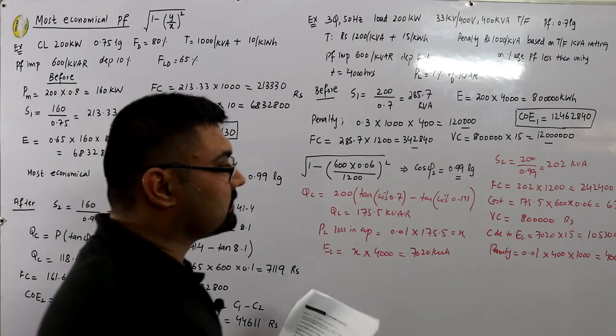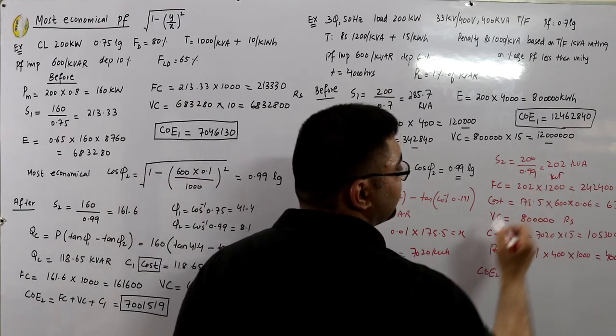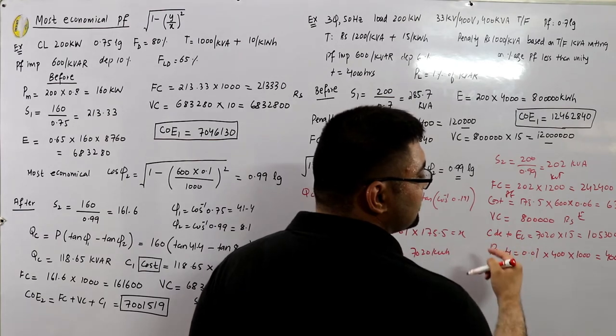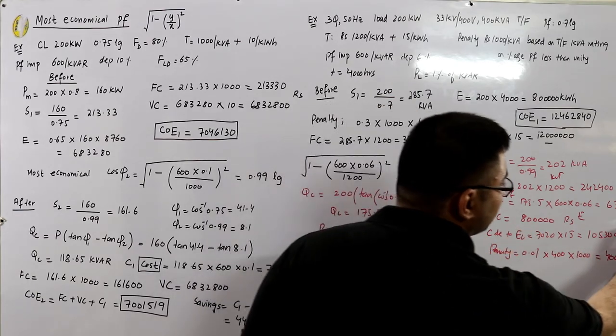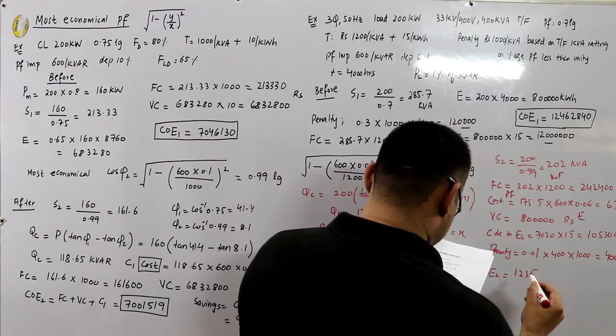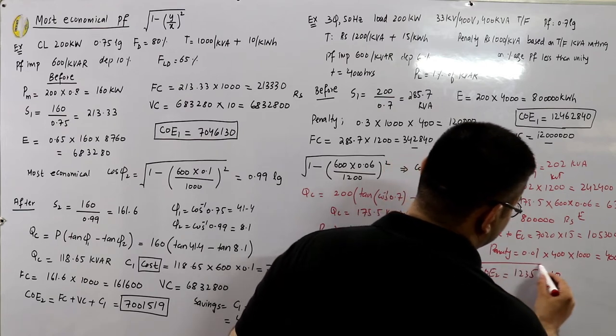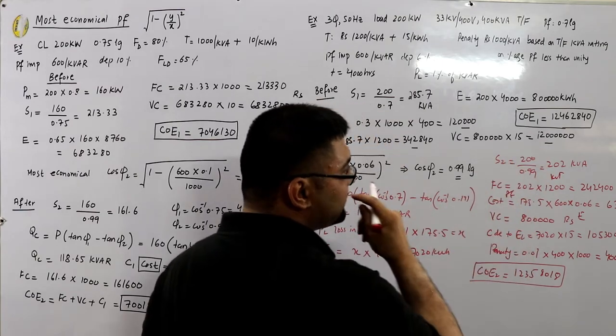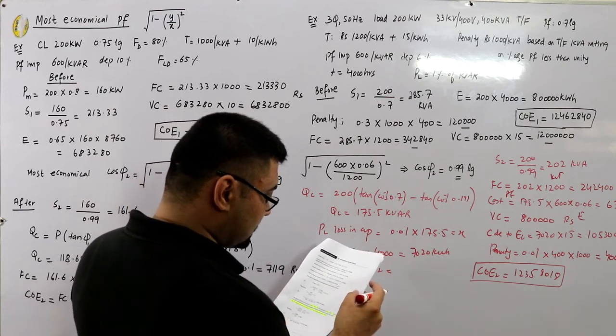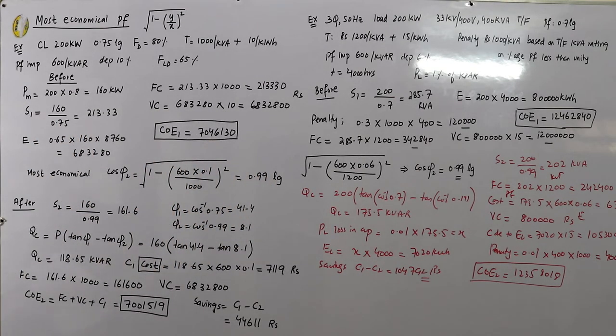The total cost of electricity after power factor correction, C₂, includes the fixed cost, cost of PFC equipment, variable cost, energy loss in capacitor cost, and penalty, giving 12,358,018 rupees. The annual savings are C₁ minus C₂ = 104,792 rupees saved per year.